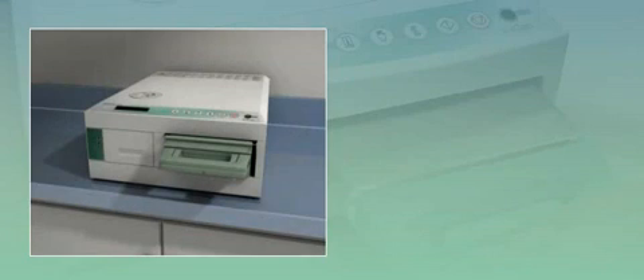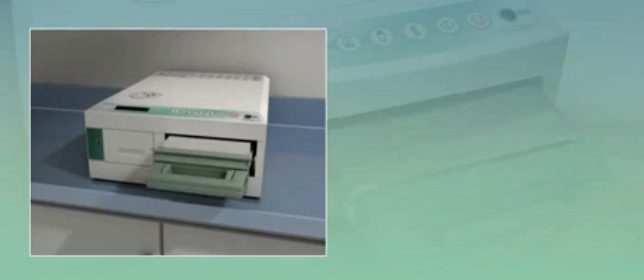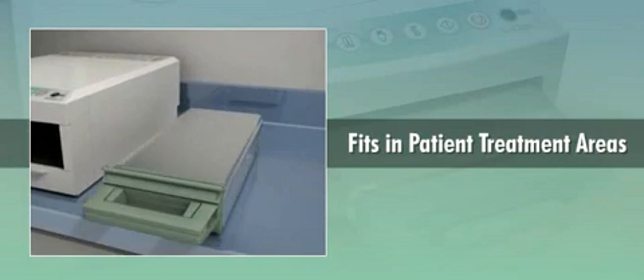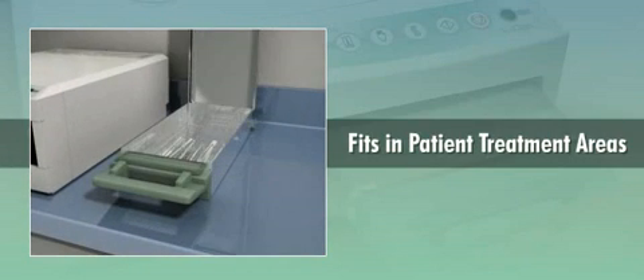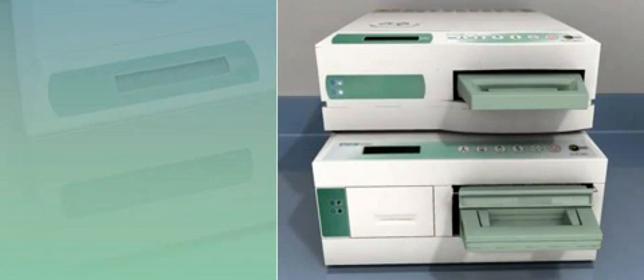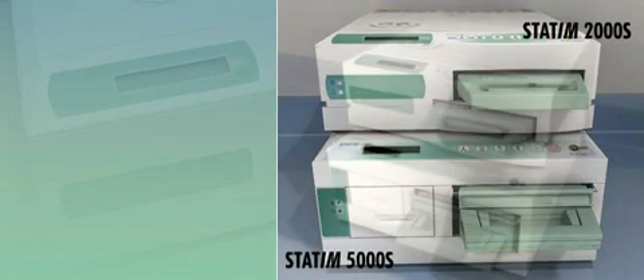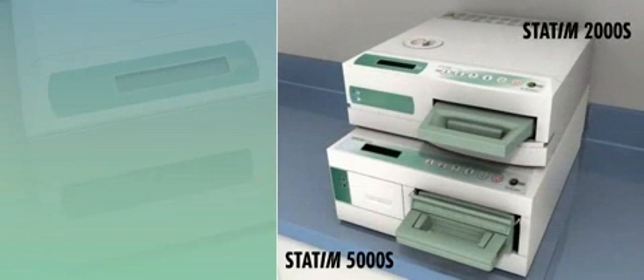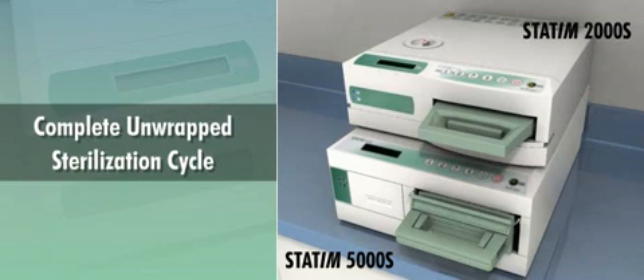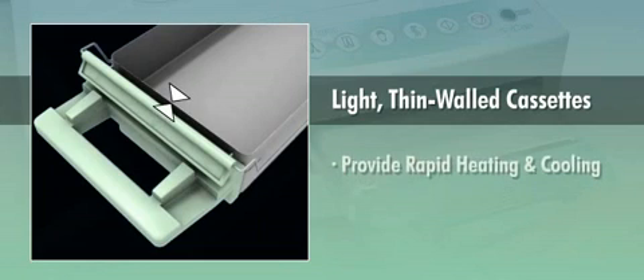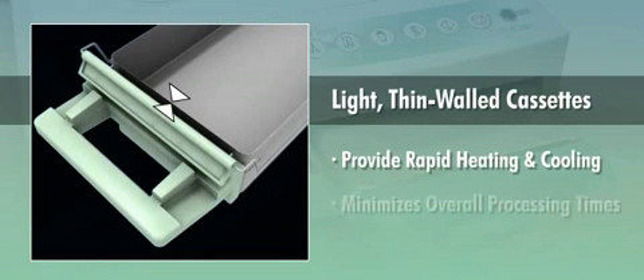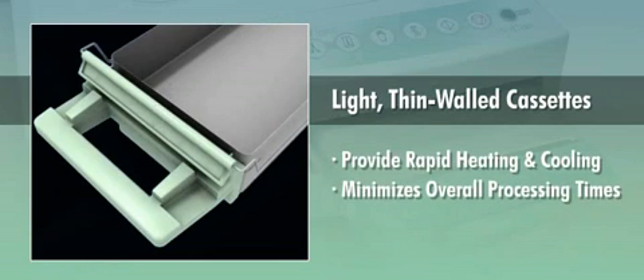STATIM is a reliable sterilization system that's compact enough to fit in patient treatment areas and fast enough to provide sterilization of instruments between patients. The STATIM 2000S and STATIM 5000S benchtop sterilizers take just 8.5 and 11.5 minutes respectively for a complete unwrapped sterilization cycle. Light, thin-walled cassettes provide rapid heating and cooling, further minimizing overall processing times.